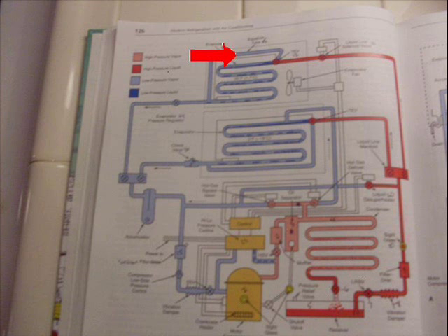So, to compensate, on large evaporator coils, we use an external equalizing tube. It's a copper tube. Transmits a pressure signal from the outlet of the evaporator back to the valve. Nothing ever goes through the tube. It's a signal transmitting tube only. Refrigerant will back up into it, but it can't get out of the tube. It just transmits a pressure signal. That is the most difficult part because people see the words equalizer and go, oh, equalizer, I know what it does. It equalizes nothing. It's a pressure transmitting tube.